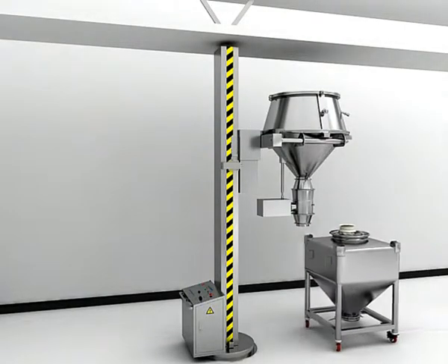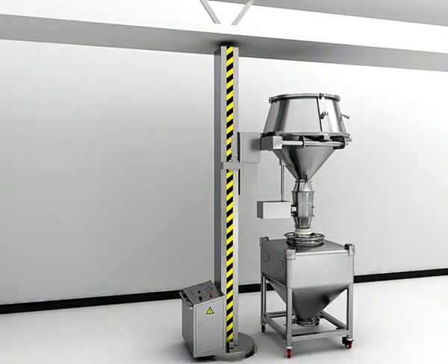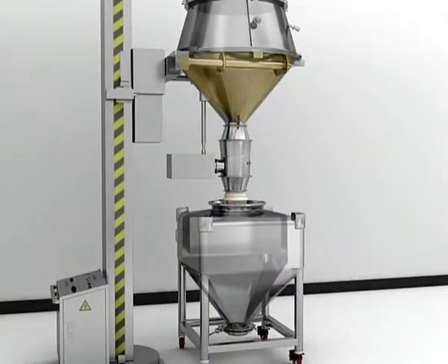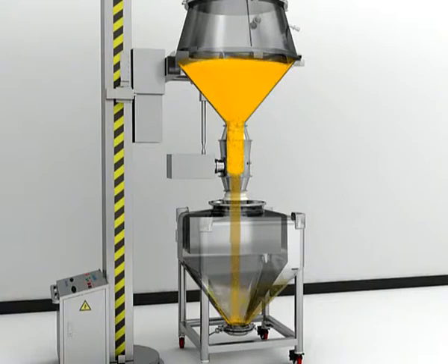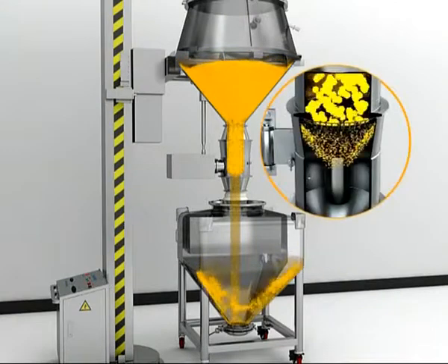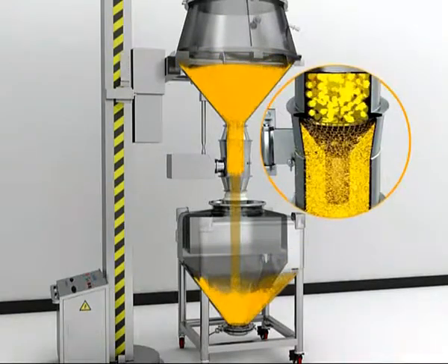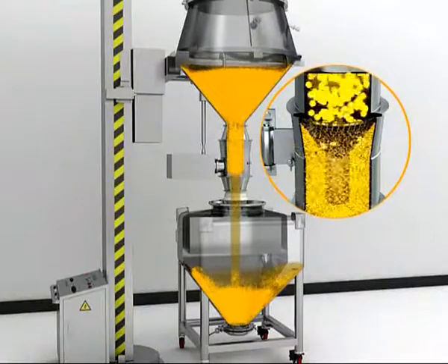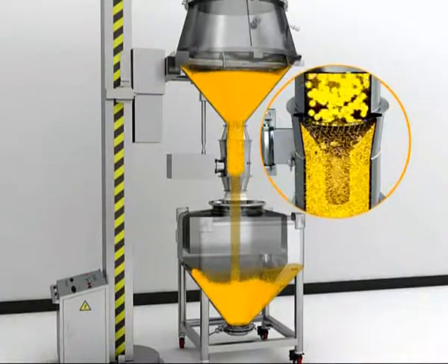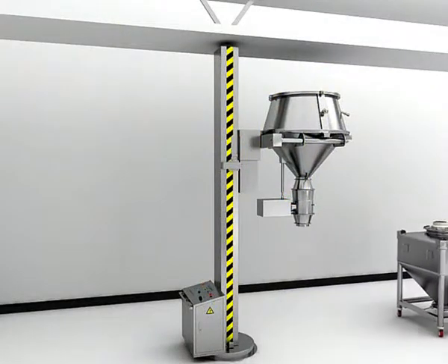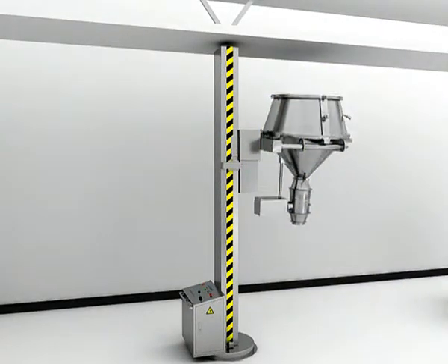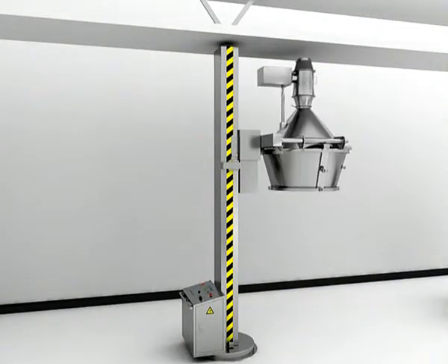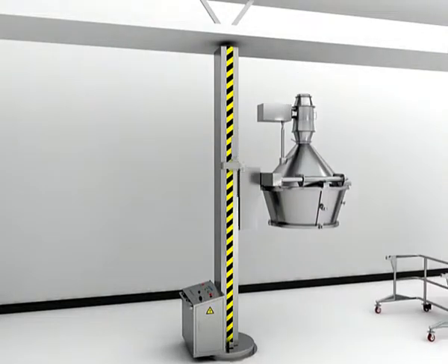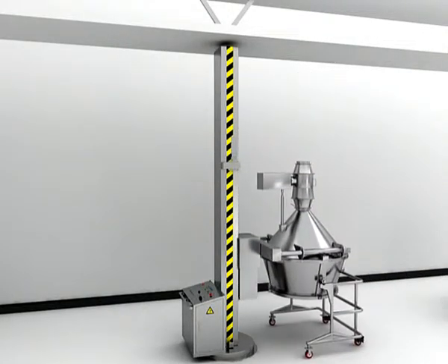Open the butterfly valve. The materials fall down into the dry mill and under the action of the impeller and sieve meshwork are milled into uniform granules and then flow into the bin. Upon finishing the process, push away the bin. The cone adapter turns back 180 degrees. Bring the bowl down to the initial position. Release the lock and pull back the fluid bed bowl.